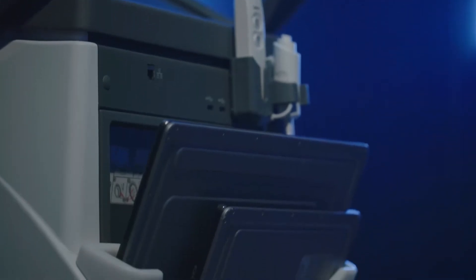The key feature of the Konica Minolta, of course, is its panel technology and capacitor. This unit will come complete with the HD dual capacitor technology. What's nice about it — we can charge two panels simultaneously onboard and carry three panels simultaneously: a 10 by 12, a 14 by 17, and a 17 by 17.